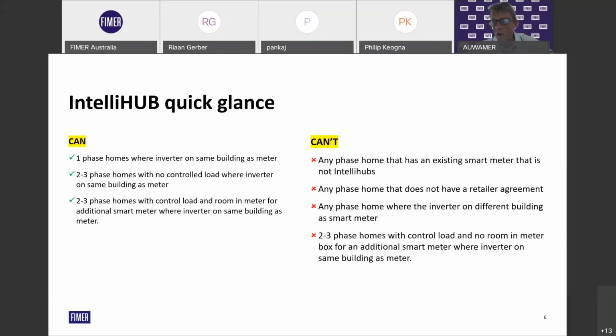Also can't meter 2 or 3 phase homes with a control load and no room in the meter box for an additional smart meter where the inverter is on the same building as the meter. So if the board is full, it's obviously going to blow out the cost of the job. You probably have to do a switchboard upgrade, or it's just physically not possible.